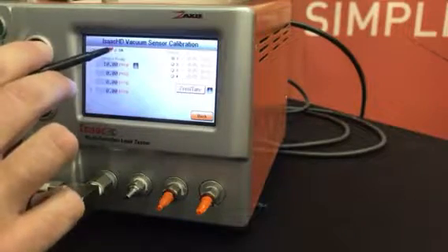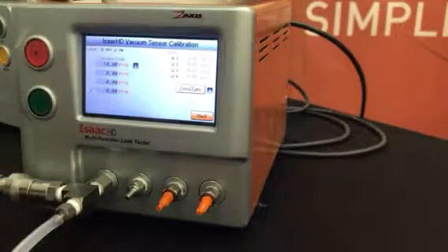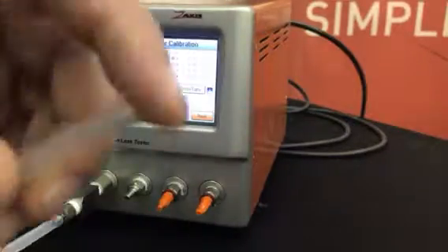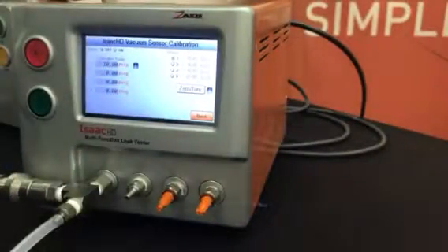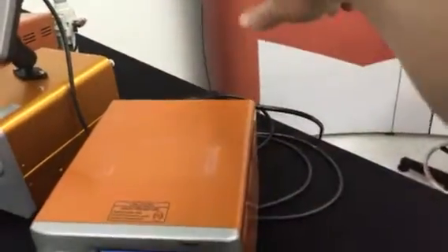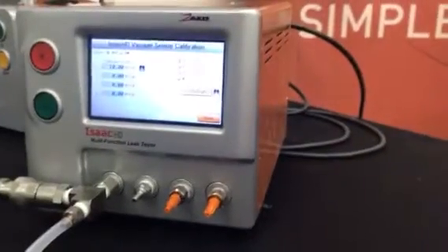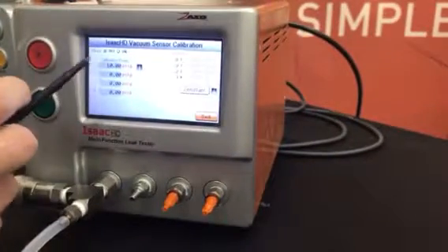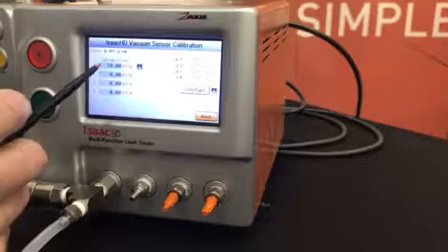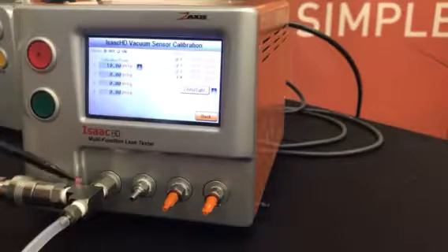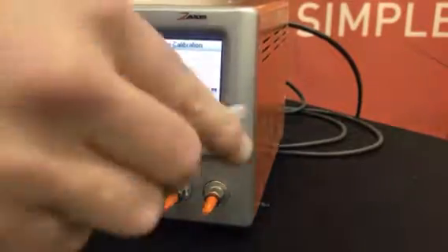Hit the tare so it'll be at a full 0, and then you'll do valve on, and then you'll feel a suction start coming out of that channel 1. So you'll have an SMC regulator right here on the top corner of your tester, just that regulator to get to your 4 set points, and you'll see them on the screen. So now you'll hook 1 and 2 back up. So your hose will be just like that.